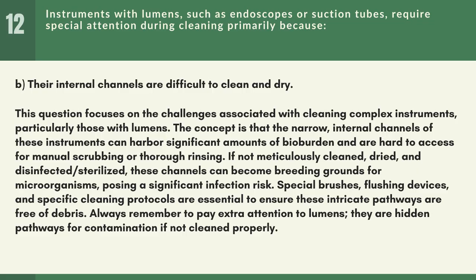If not meticulously cleaned, dried, and disinfected or sterilized, these channels can become breeding grounds for microorganisms, posing a significant infection risk. Special brushes, flushing devices, and specific cleaning protocols are essential to ensure these intricate pathways are free of debris. Always remember to pay extra attention to lumens. They are hidden pathways for contamination if not cleaned properly.